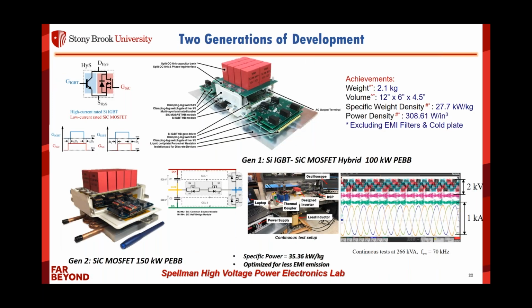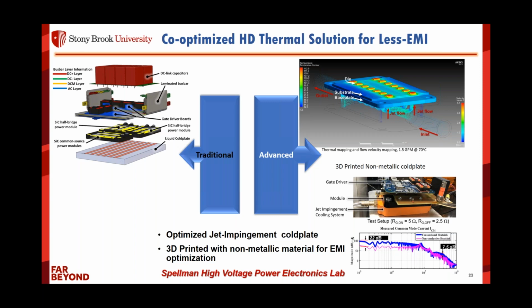The number actually comes in on the next page. So the other thing is, to further reduce the weight of the system design, we want to get rid of the metal cold plate here, which is a big chunk of your system weight. So I worked together with my colleague, Dr. David Heiting, and we thought of replacing this cold plate with a 3D printed, non-metallic plastic cold plate for the system. Since I'm replacing this with a plastic piece, I'm losing the benefit of removing heat from the metal surface.